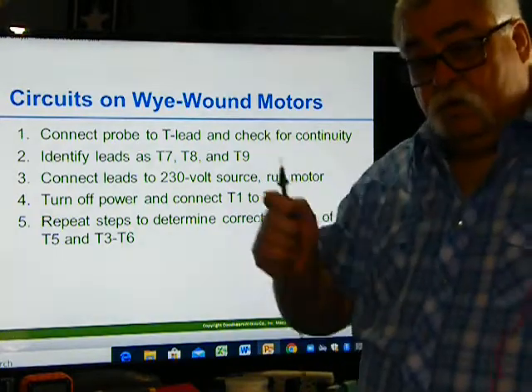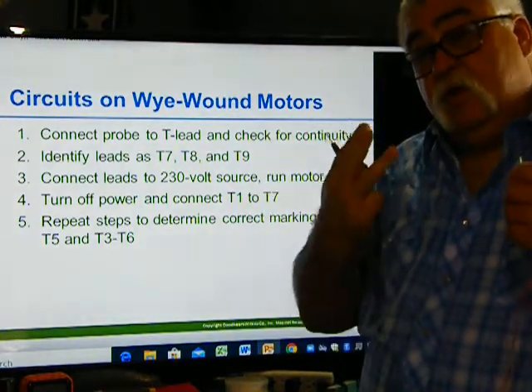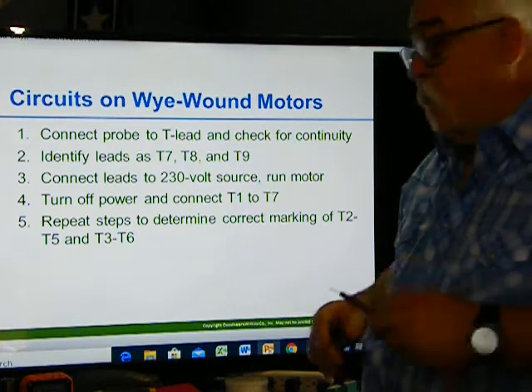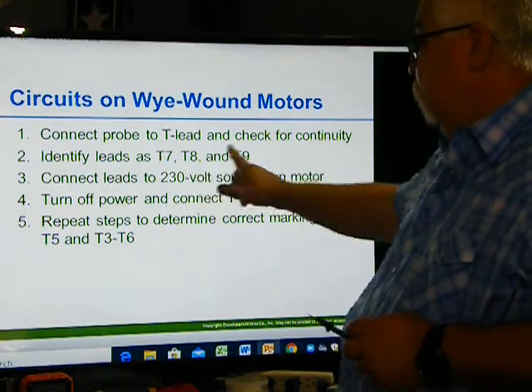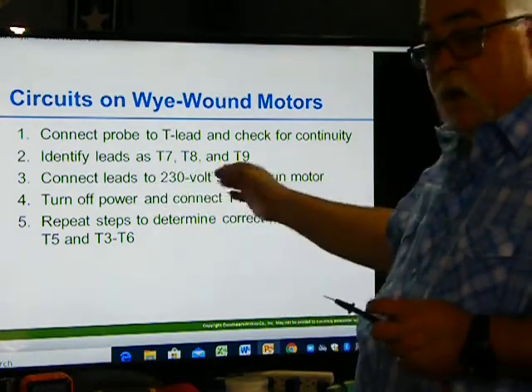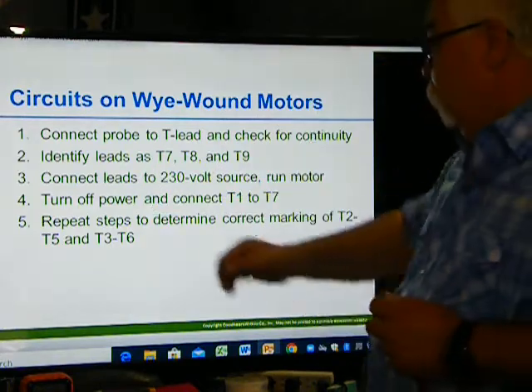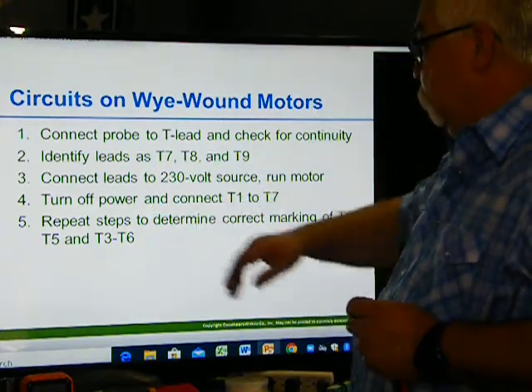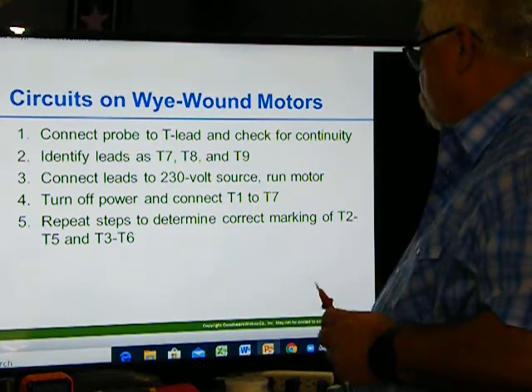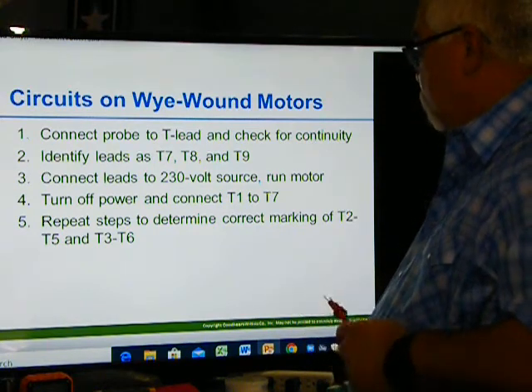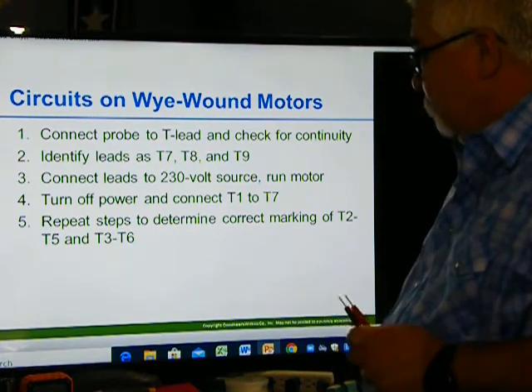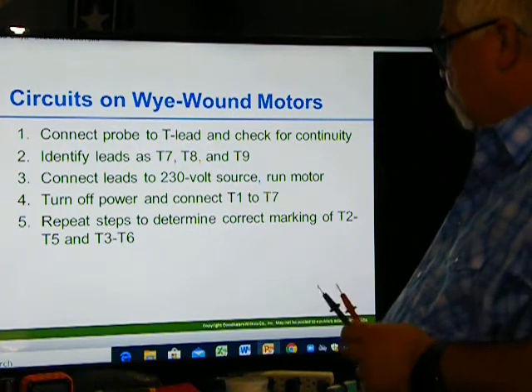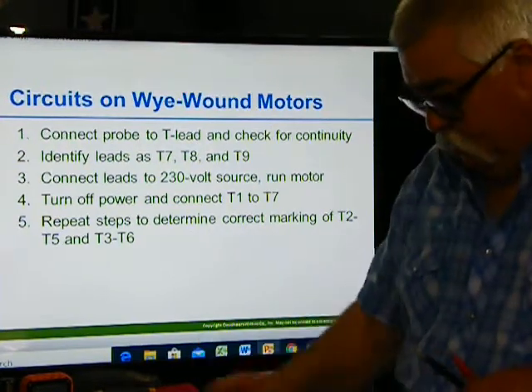Okay, if you go across and check the other ones, and all of a sudden you get it on a 3rd wire, now you know you've got a Y, and you've got T7 and 8. Which of the 2 are they? I don't know, but at least you know you've got your 3 wires, your center part. Let's connect leads to a 230-volt source and run the motor, turn off power, and connect 1 and 7. And then repeat. So in order to find, where's mine?